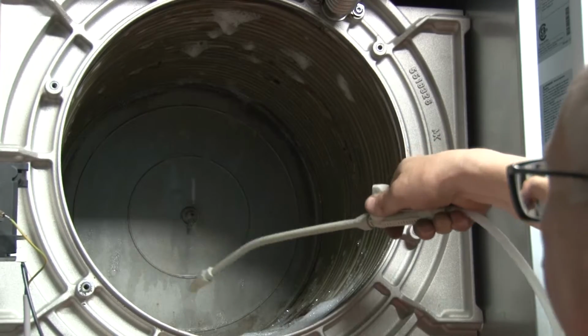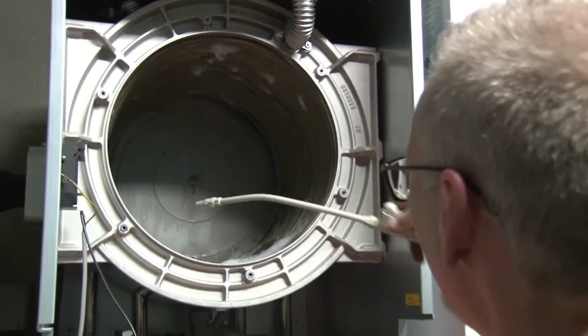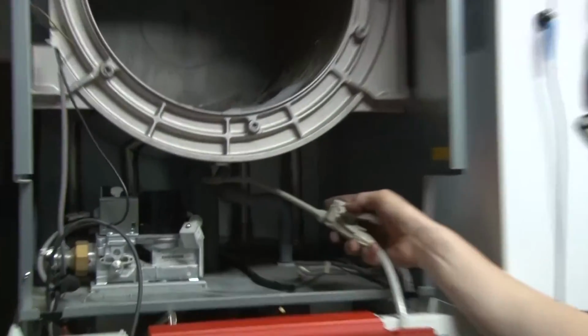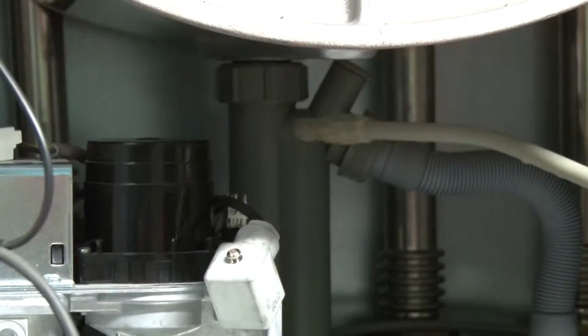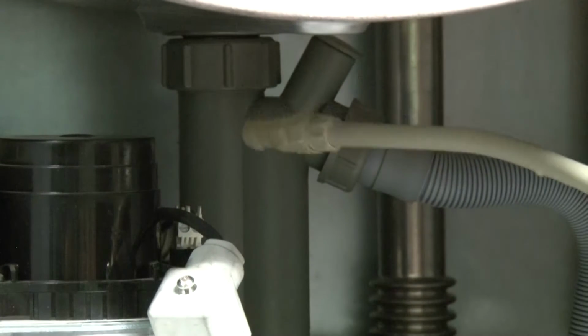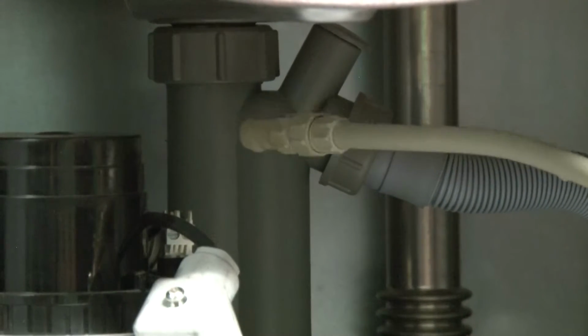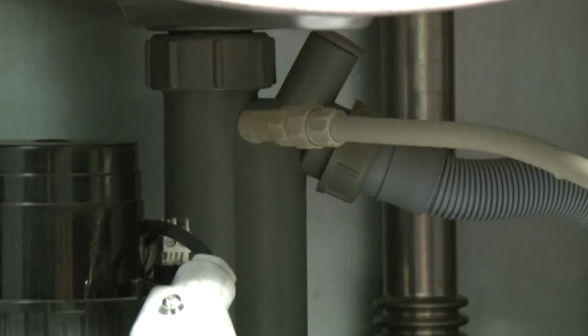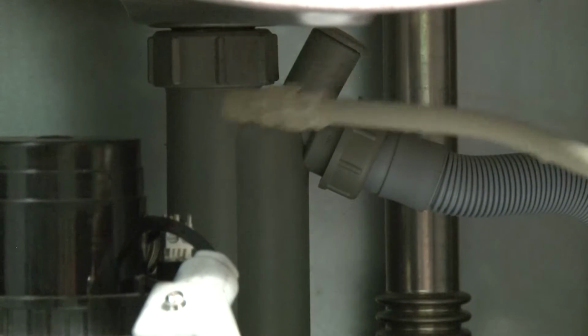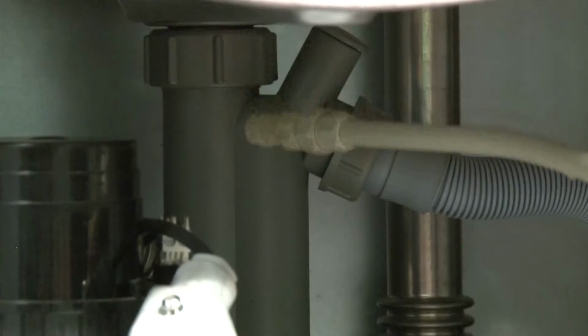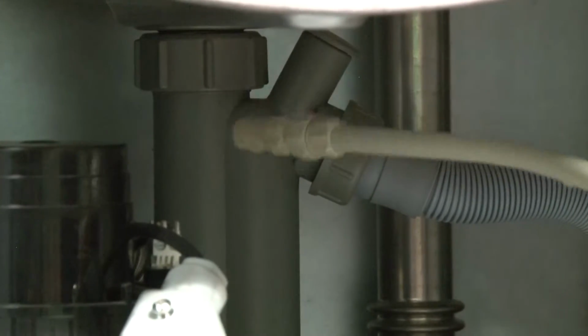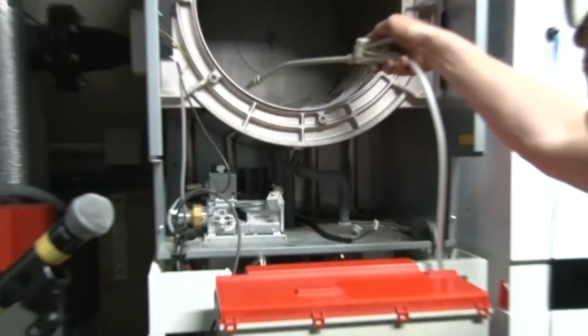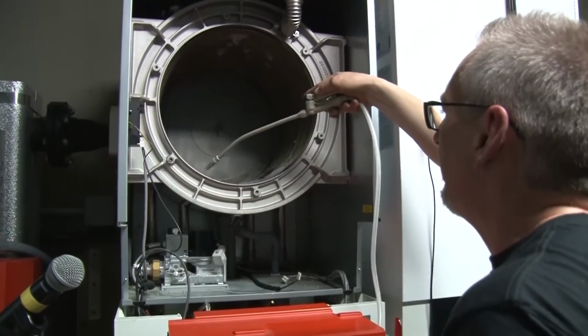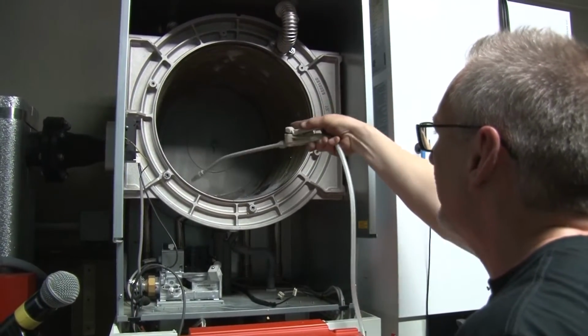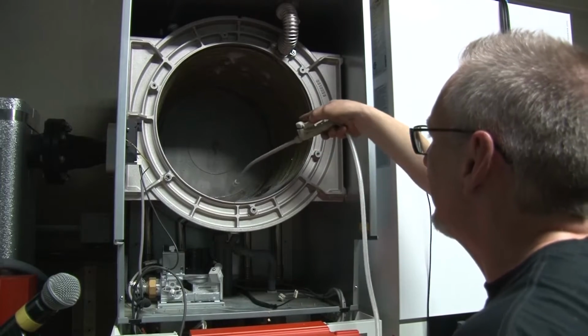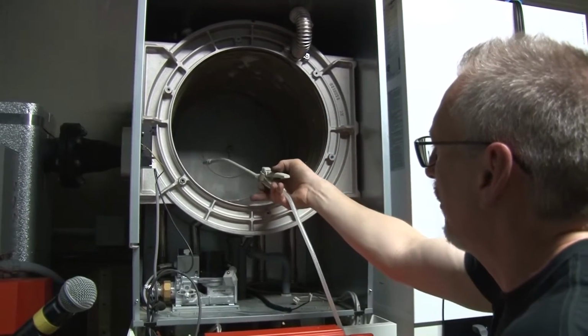If this was extreme, what I would do is actually remove this P-trap inside. I would pop that off and plug that area off, whether you just taped it or put a cork in there, whatever, and secured it. The condensate pipe off of that. So take the P-trap out, the little stainless steel pipe that this is connected to, secure it and basically isolate it so water can't get out of it. And I would flood this heat exchanger. And when you flood it, what I'm talking about is making sure you get enough water or chemical mixture in there that it almost starts to come out the front of the boiler.